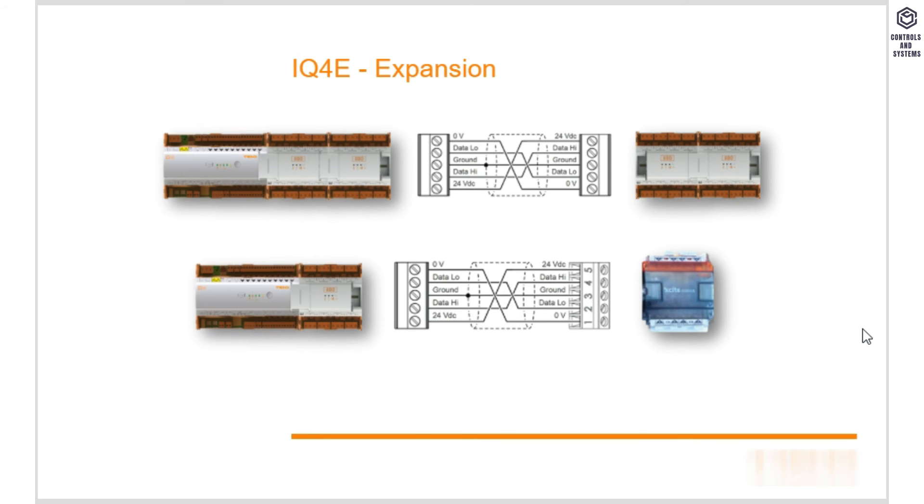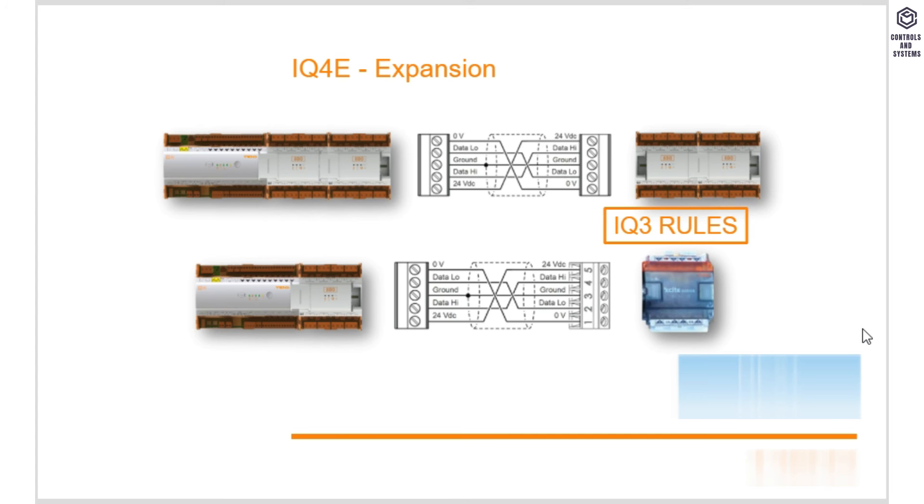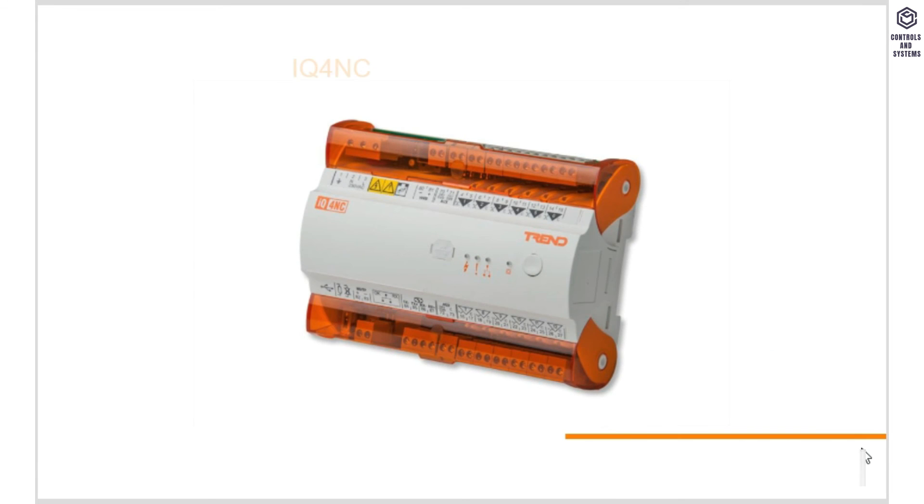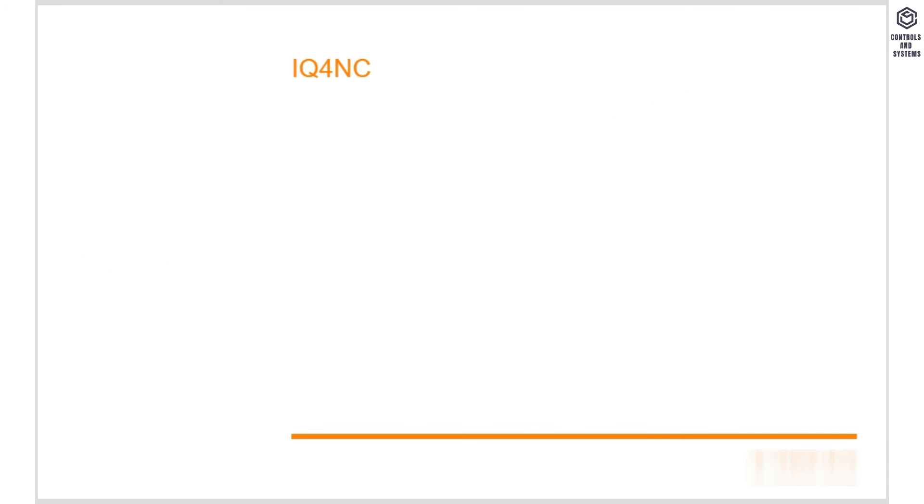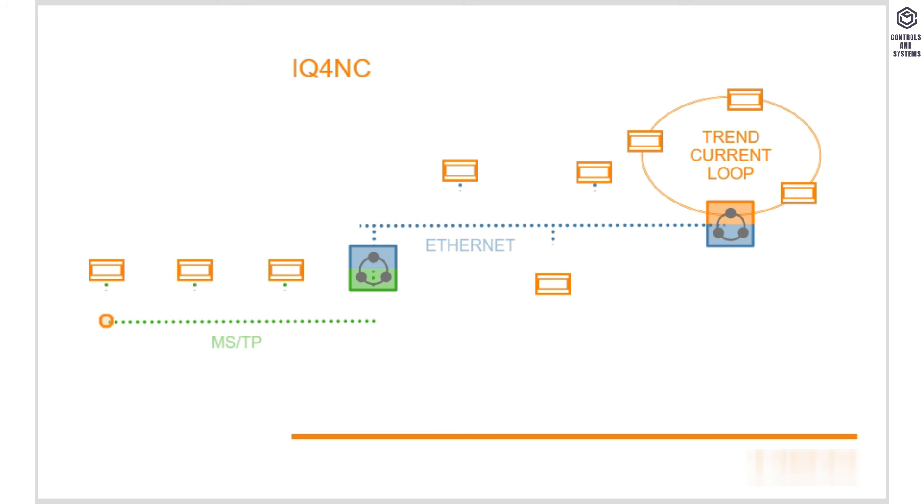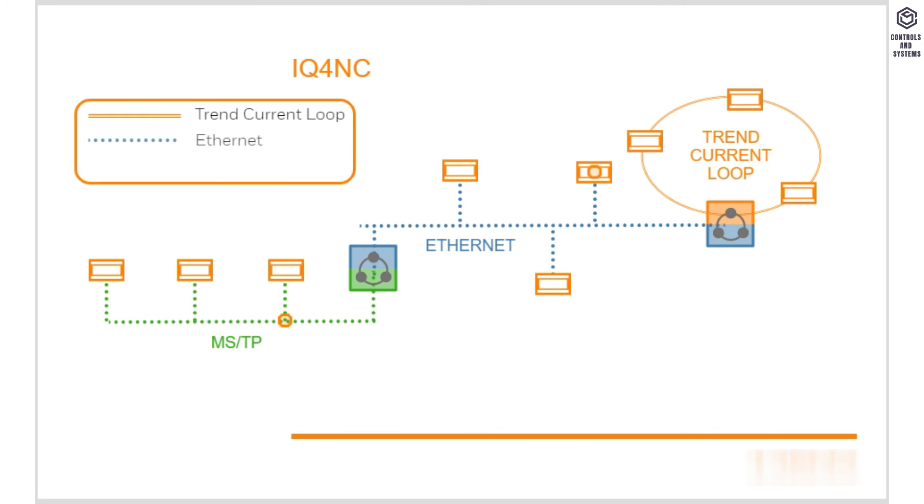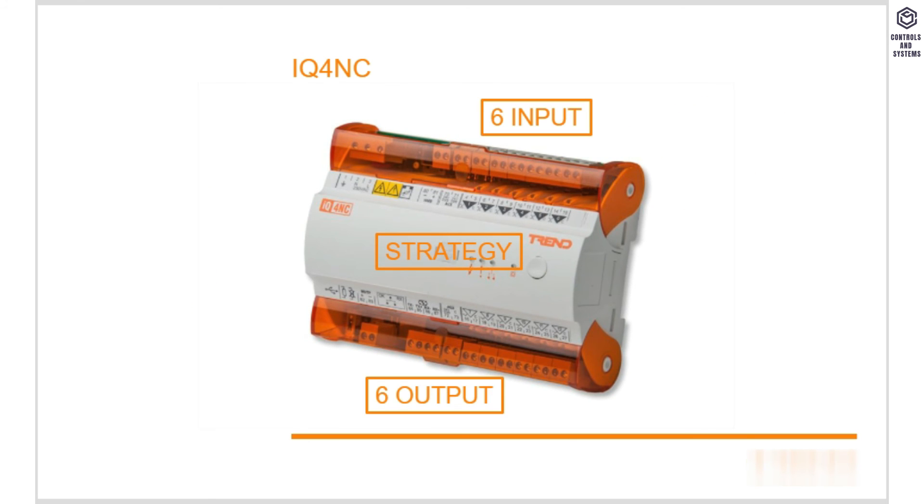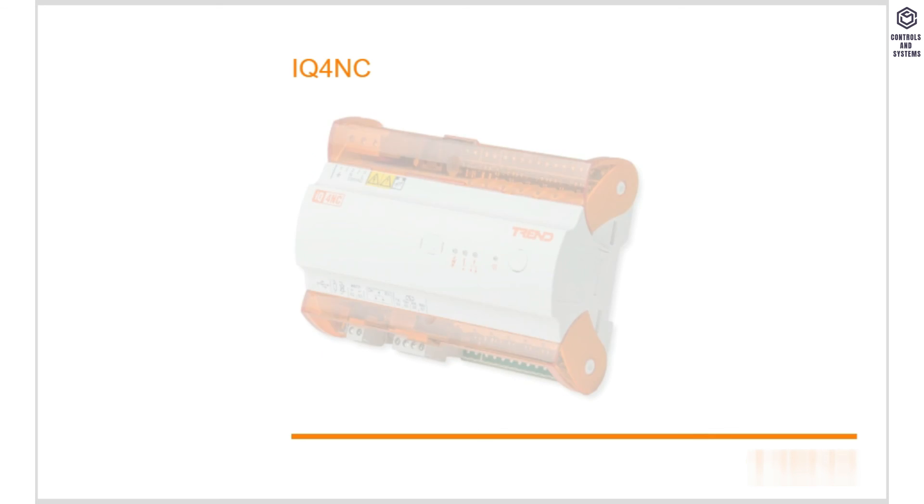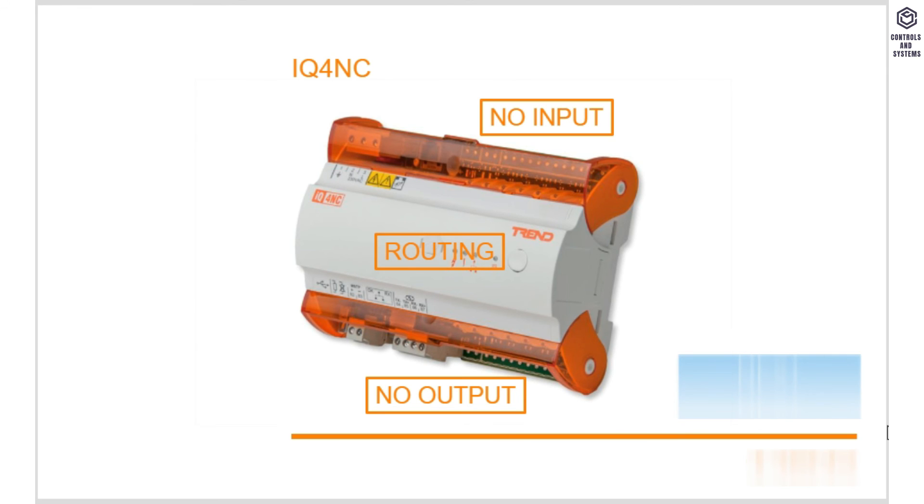If you are doing this, then please remember that the maximum distance point and module rules will revert to those set for the older IQ3 range. As mentioned, the IQ4NC acts as a bridge between networks, combining the IQ4-22 and the IQ4E platform. It has both controller and inter-network functionality, which means it is able to route communications between various types of network including Current Loop, Ethernet, and MSTP, in addition to running its own strategy along with connections to the real world. However, it is possible to purchase a version without inputs or outputs if just the routing function is required.